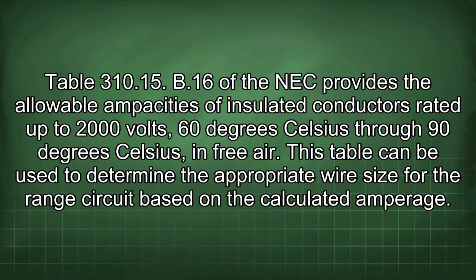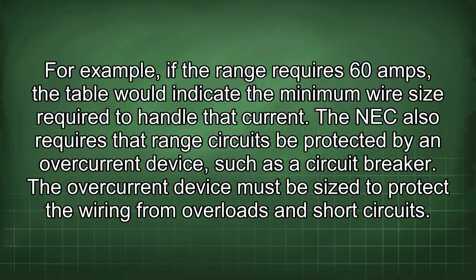Table 310.15(B)(16) of the NEC provides the allowable ampacities of insulated conductors rated up to 2000 volts, 60 degrees Celsius through 90 degrees Celsius, in free air. This table can be used to determine the appropriate wire size for the range circuit based on the calculated amperage. For example, if the range requires 60 amps, the table would indicate the minimum wire size required to handle that current.